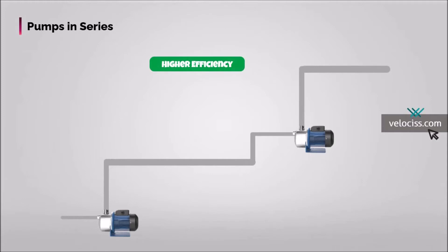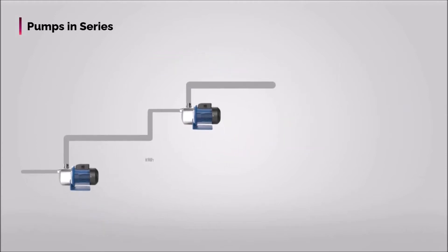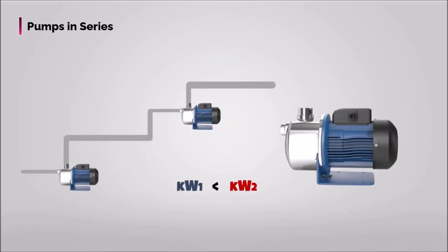Series pumping is a pump configuration used to overcome a high static discharge head or extremely long piping lengths with high friction losses. Series connected pumps generally require less horsepower than one large pump meeting the same condition point.